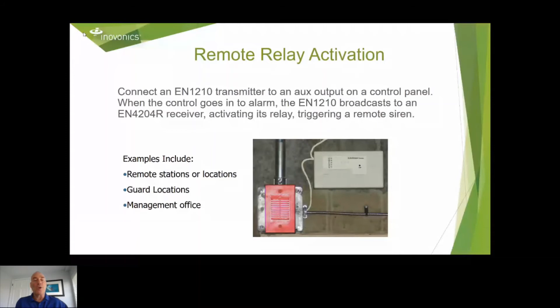Okay, commercial fire. I fully realize, and I believe this is still correct, you're not allowed to do wireless for commercial fire as a system. Now, this is a single point add-on, so you would still need to get this granted as an exception, but this is how these things start and perhaps eventually gain acceptance. This is UL864 for commercial fire. So the transmitter would go on a switch, and then the receiver goes at the fire panel.